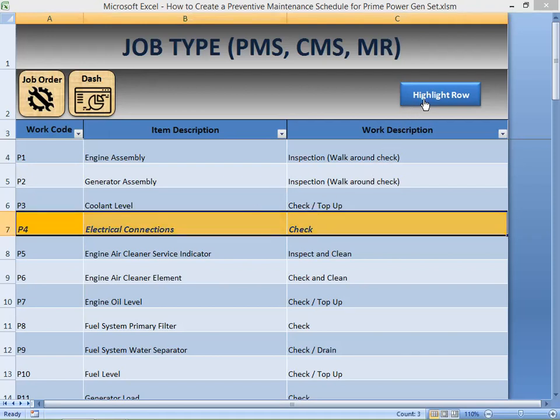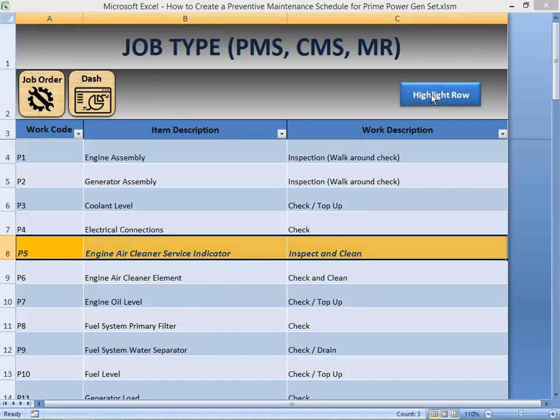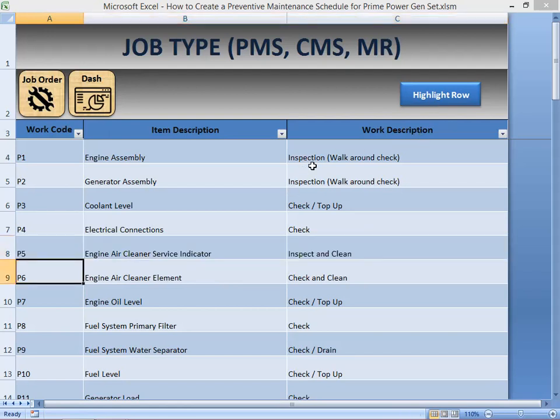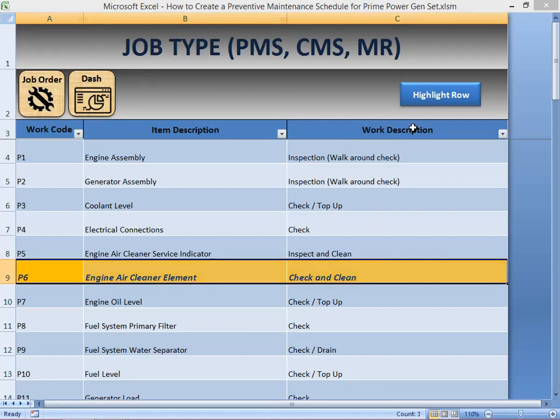This has to be performed by the electricians; you hire an industrial electrician with expertise on generating sets, power units. Okay. Then air cleaner service indicator. The indicator shows red or green. Red means the air cleaner is clogged up, full of dust inside, and needs cleaning. That's why it's showing you a red indication. You have to inspect and clean with air coming from the air compressor, something like that. And then also the element, you're gonna check and clean it.